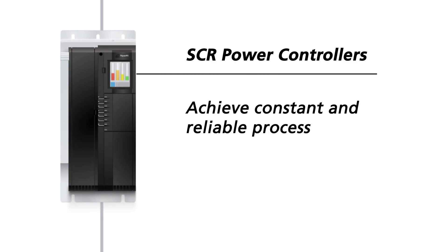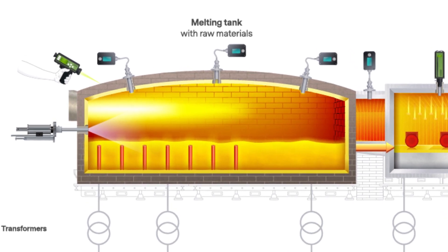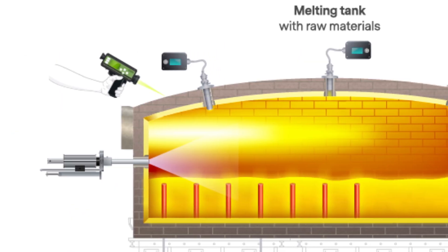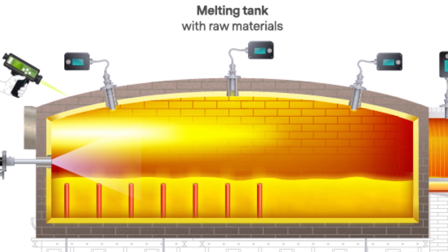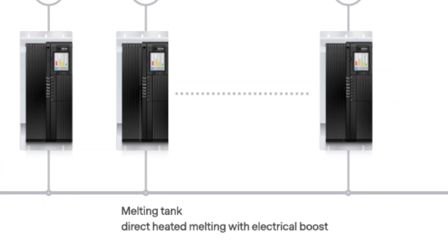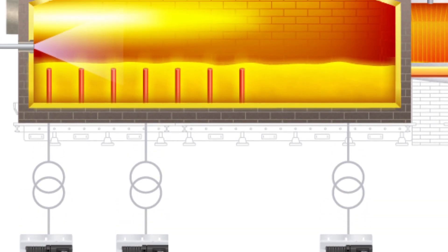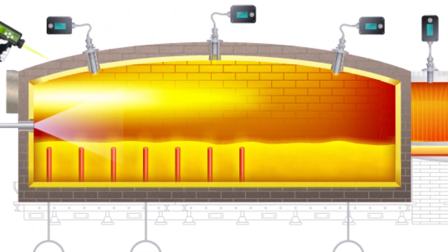The addition of power controllers also enables you to easily adjust process parameters and achieve a constant, more reliable process. For glass melting, it is important to monitor and control the melting tank, including the temperatures along the roof, end wall, tank bottom, and surface of the molten glass. It is also important to precisely regulate the power, current, and voltage along the melting process.